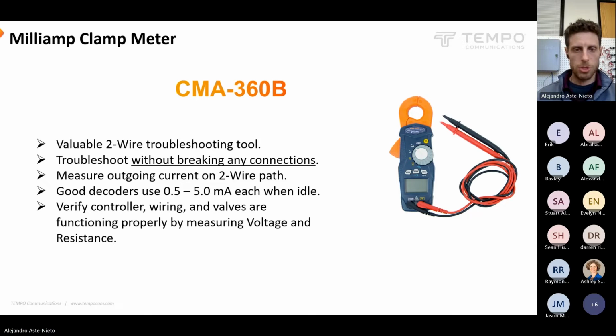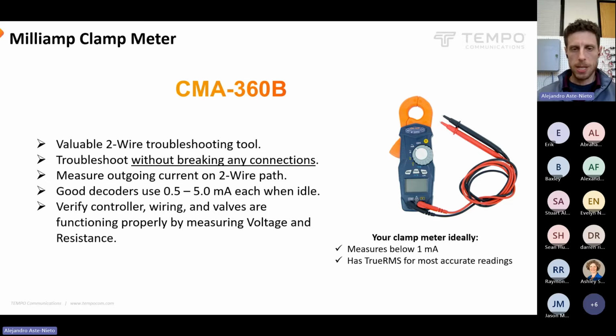We can also take some other measurements with the leads here with voltage and resistance, which is very helpful. So ideally, your clamp meter measures below 1 milliamp, because as you can see here, we're dealing with things that measure in fractions of milliamps. Ideally, it has true RMS for the most accurate readings, especially if you're taking measurements while the system is idle and operating normally. Some systems might use a clamp meter friendly 60 hertz. Other ones use a very unfriendly wave. And then ideally, your clamp meter also has the ability to take these other measurements as well.